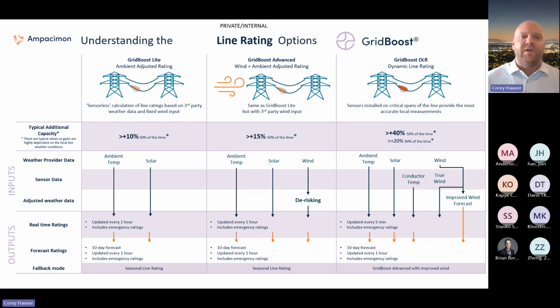The last one we have here is our Grid Boost Dynamic Line Rating DLR system. And this is where we are going to physically put sensors on the line. And via vibration technology, these sensors are going to measure the wind speed, the sag to within 20 centimeters, regardless of the height. It's going to be able to calculate a mean conductor temperature, and so on. So we're really getting a lot more information here. We're also getting it directly from the line and creating that level of accuracy above our ambient adjusted solutions.